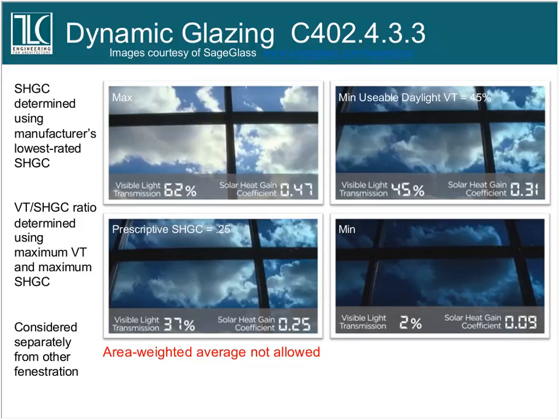And this tends to be a relatively expensive technology, adding tens of dollars per square foot to the cost of the windows. We're actually beginning to do projects with this kind of glass in special spaces like lobbies and building entrances that have a bad solar orientation, face directly west, for instance, where we can use this product to allow us to still meet the code but reduce the size of the air conditioning system, and that allows us to trade off some cost that you might see on just the cost of the dynamic glazing itself.